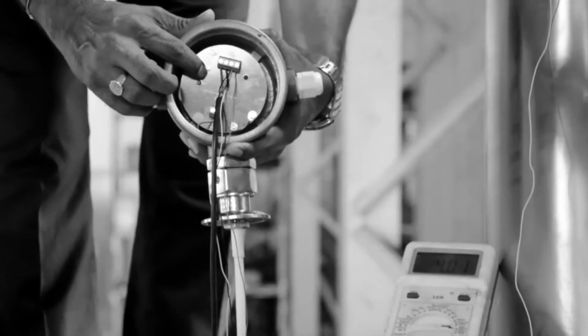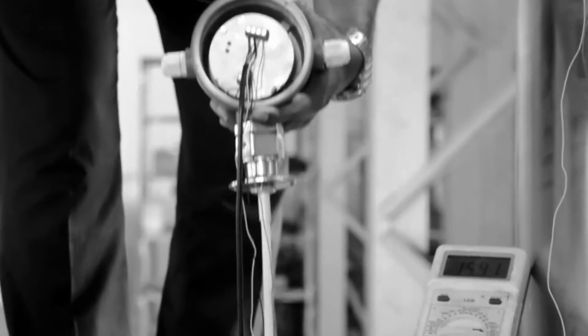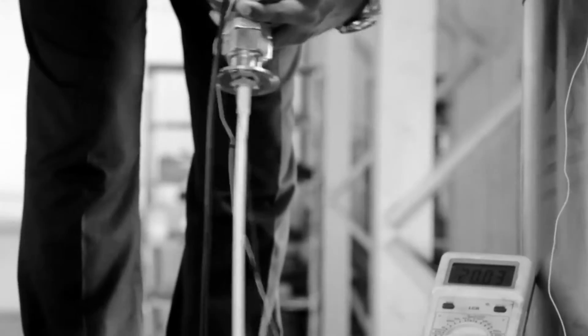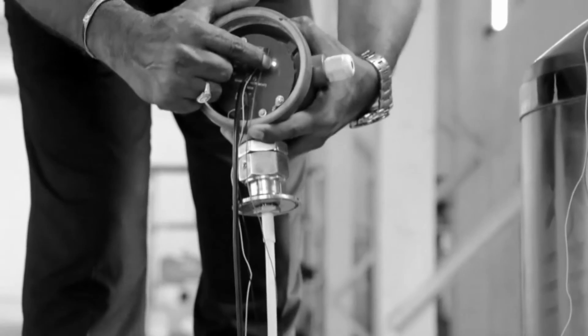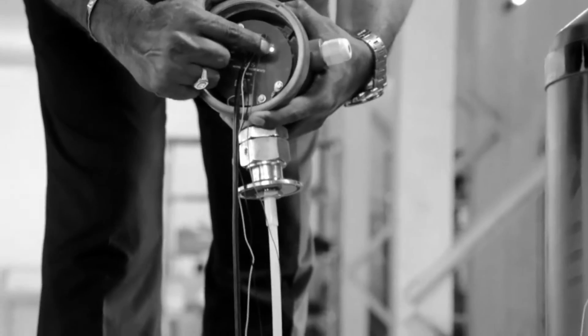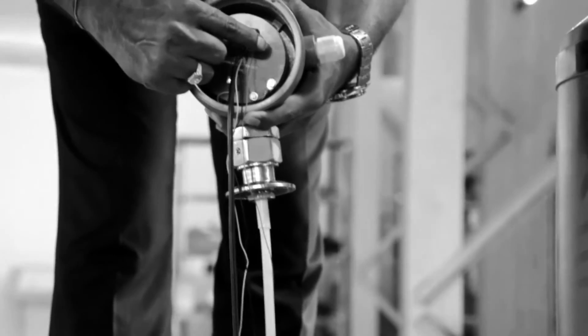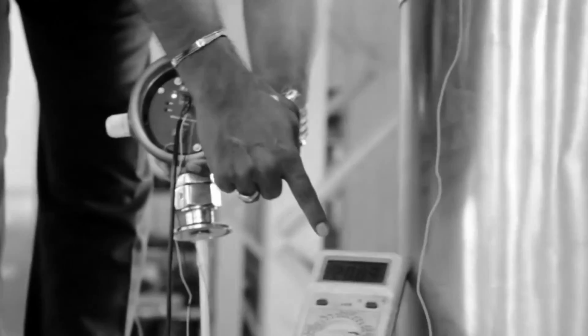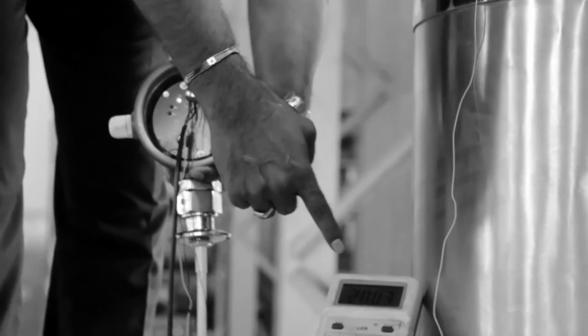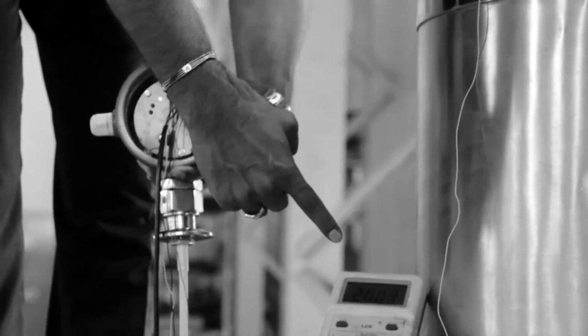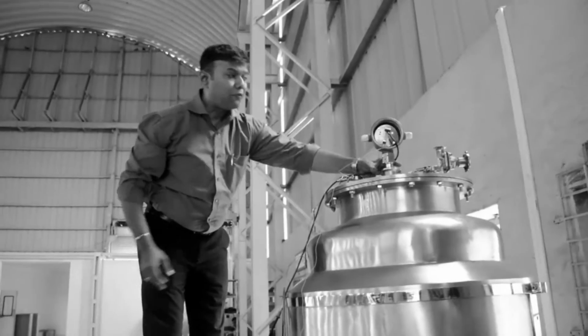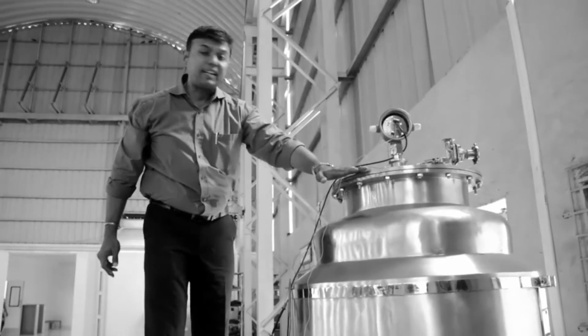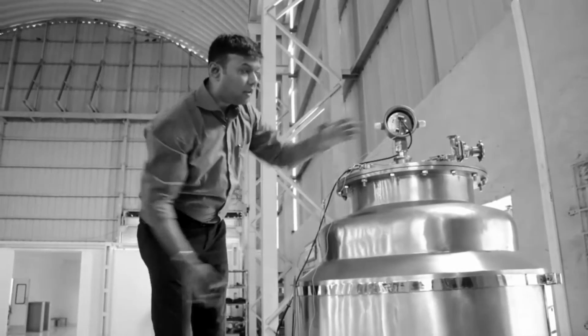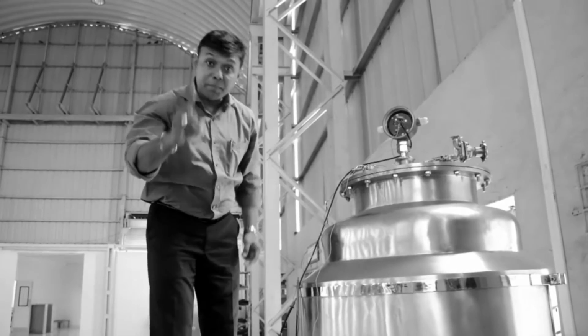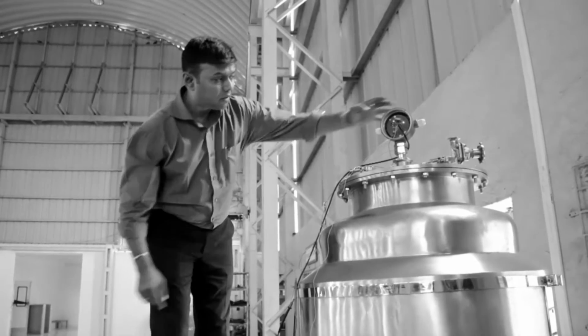I am pressing the minimum button once. After I press the minimum button once, you will see that the calibration LED has stopped blinking and it has gone to a steady mode. It is no more blinking. And you can see that the multimeter is showing 20 milliamps, which means it is ready for the 20 milliampere calibration. I have put this sensor into the tank. The tank is full and I am going to press the minimum button once more.